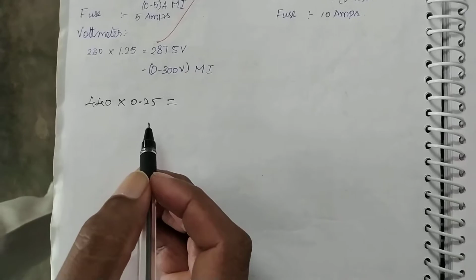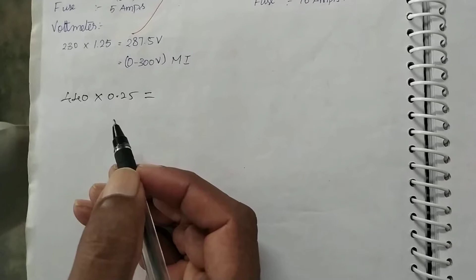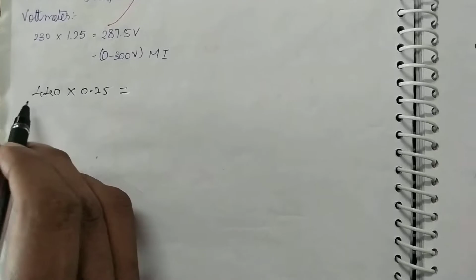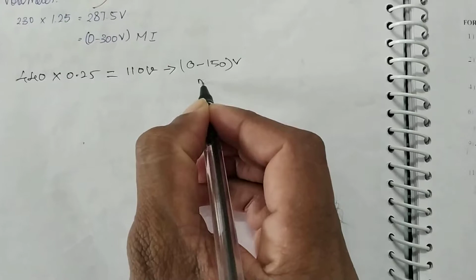Since in the short circuit test the voltage applied to the transformer will again be 10 to 20%. In the open circuit test the current will be 10 to 20%, but when you come to the short circuit test the voltage will be 10 to 20%, but the current will be 100%. Hence, we are getting 110 volt. The nearest highest voltmeter available will be 0 to 150 volt MI. This will be more than sufficient to measure our readings.